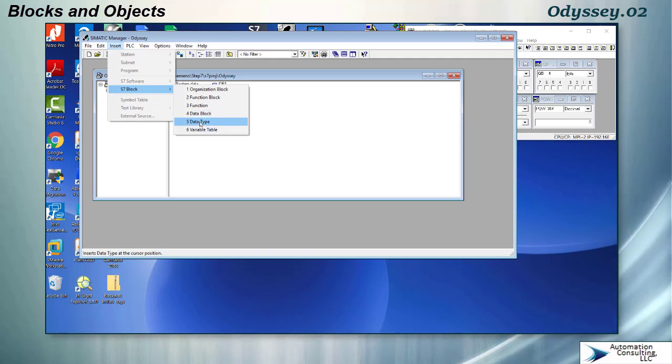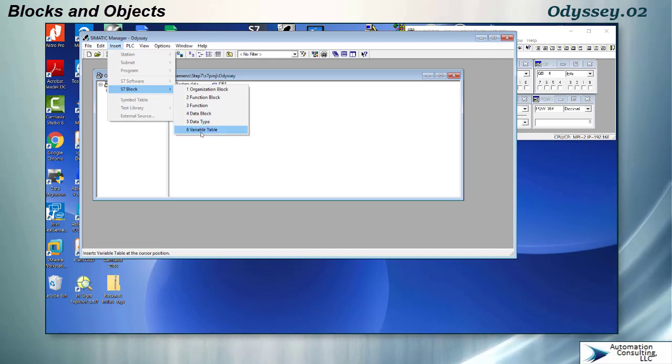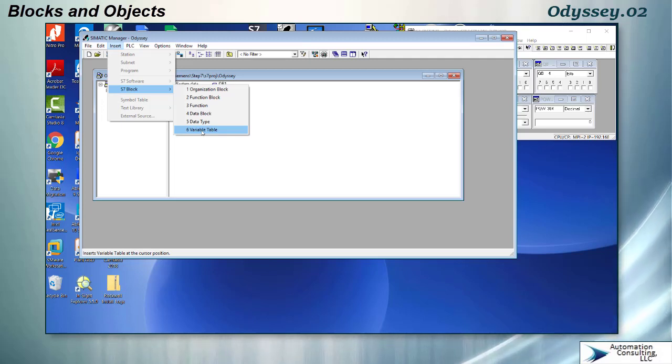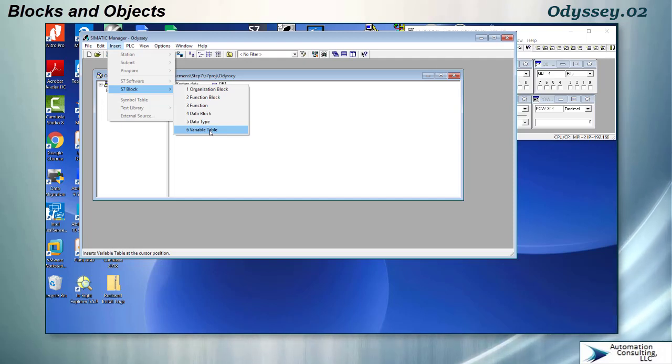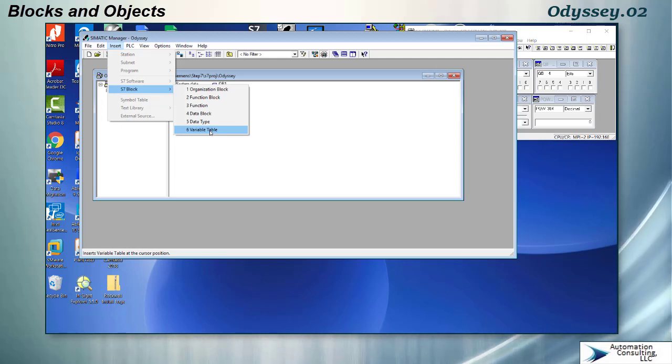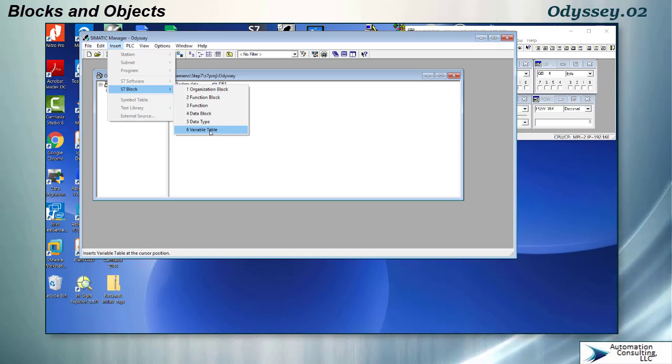Then you have data types which are UDTs and you have variable tables. Variable tables are very important, they are the only way that you can change data in a PLC. You can monitor it and you can change it, so you can't just type it in the editor, you have to use a variable table to change the numbers. This is a little older software package than things like RSLogix 5000 or 500 even, so it really goes back a ways and has some archaic ways of getting things done, but that's what the variable table is used for.